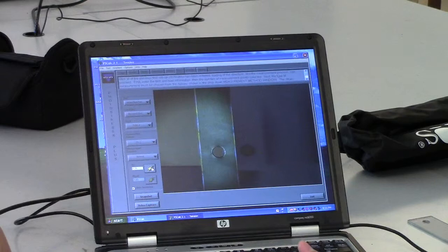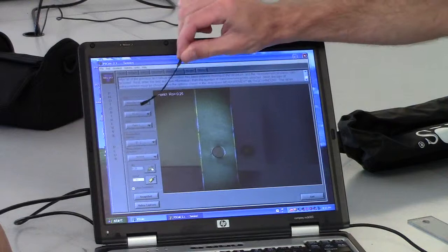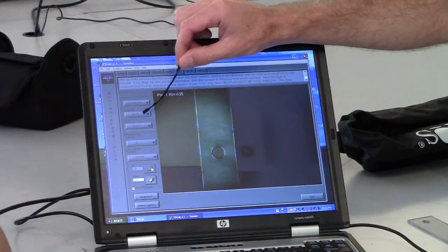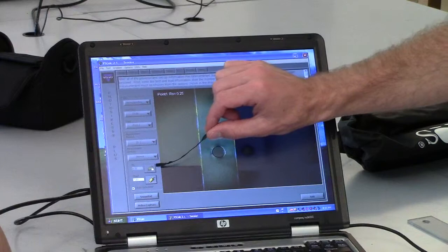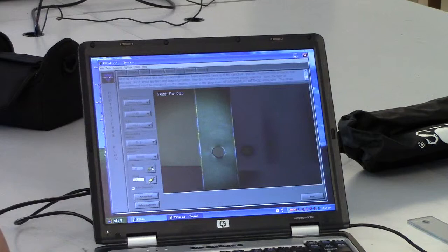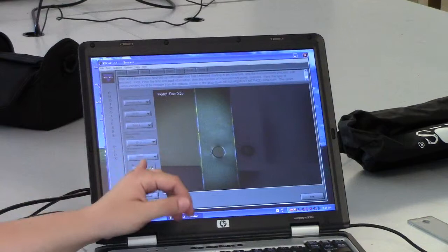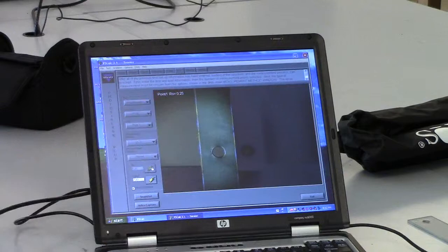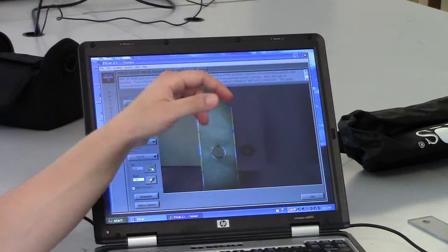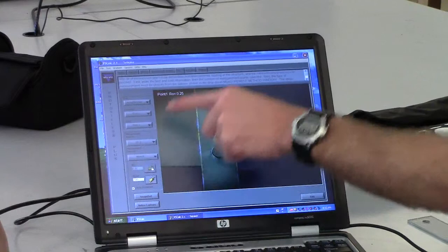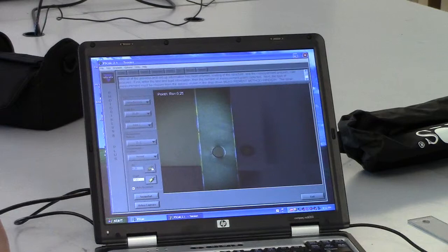Now notice what happened. The software automatically updated to go to the next point of load that we had indicated, of the 15, 30, 40, and 50. At this point, we are no longer hitting the lightning bolt by R0. Now we're going by the R load, and R comes from the calculations in the user's manual for calculating stress. When you hit this lightning bolt, all it does is record this number. That 0.25 is from the previous lightning bolt capture, and it's a calculation based on that; this number is not going to be reflected here.